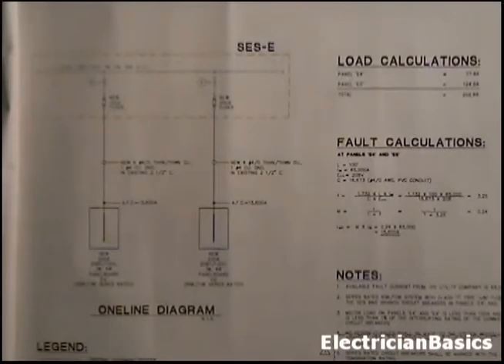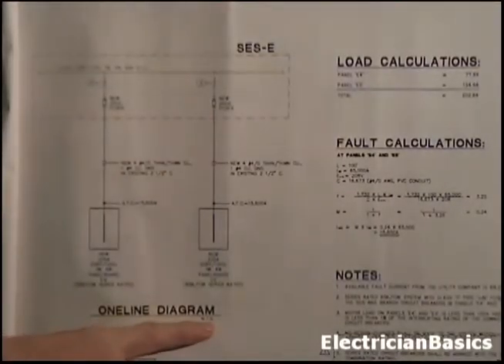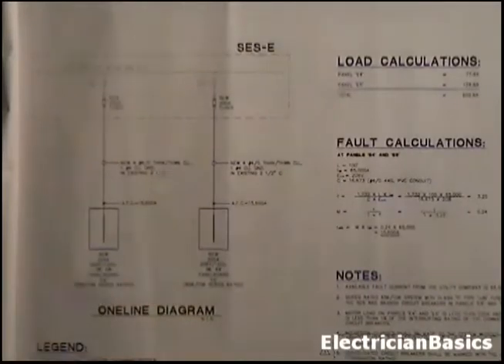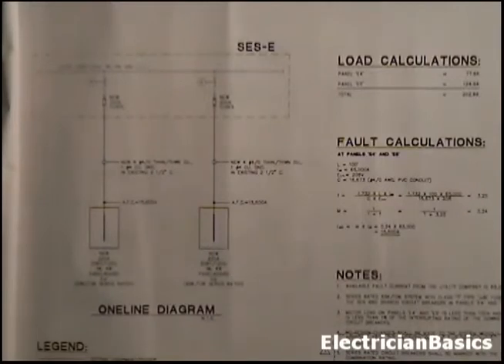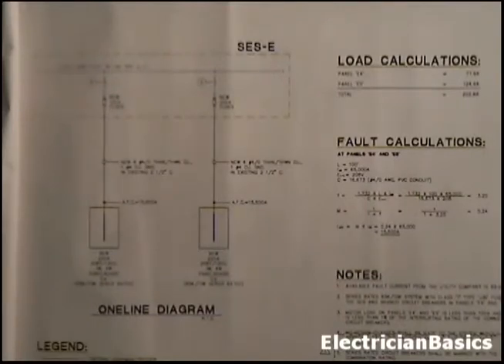So now let's come back to sheet E 5.1, and we're in the upper left-hand corner looking at the one-line diagram. Okay, now we mentioned NTS. It's not to scale. You can see it here. With the one-line diagram, the reason it's not to scale, it's a very compact look at the wiring. And it's a one-line diagram because we're just showing a simple path from point A to point B to point C, and showing how the electricity gets basically from the power company to each panel. So we start up here, and this is a very, very simple one-line diagram.